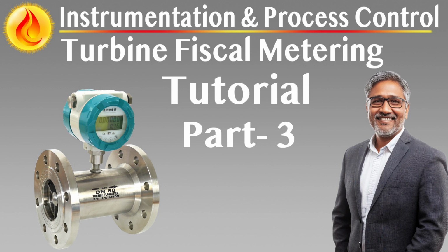For applications where water content data is only used for operational monitoring, not for fiscal net oil computation, a single sensor may suffice. Water cut sensors must be capable of accurately measuring water content in the range of 0 to 5% by volume with an absolute accuracy of 0.2%. The output signal must be 4 to 20 milliamps analog, scaled linearly across the sensor range, and transmitted directly to the station flow computer or DCS for use in net oil calculations or alarm logic.